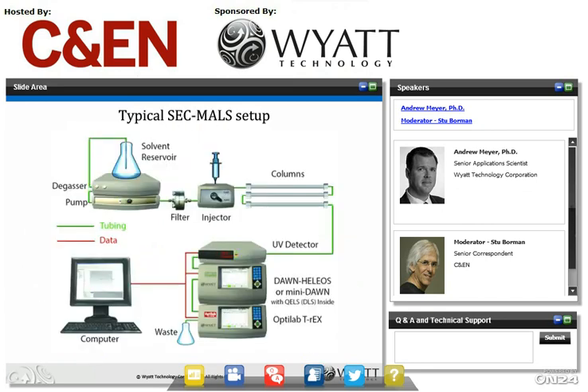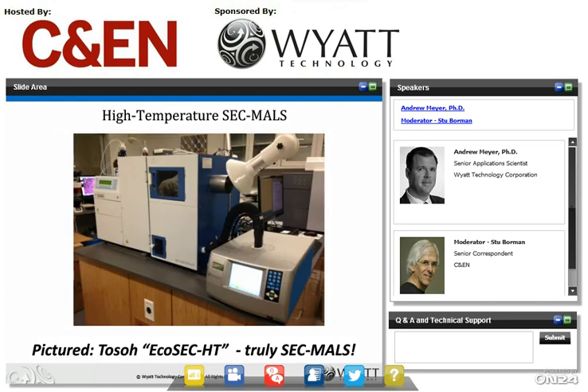In this slide we have a look at the complete SEC-MALS system. We've added a light scattering detector in front of the refractometer, and we read data from both instruments at the same time. We also have a UV absorbance detector available. This arrangement will work with just about any solvent, just about any GPC column, typical flow rates and conditions, room temperature, elevated temperature, and so on. We can take this up to temperatures over 200 degrees Celsius. Here as an example we see a MALS instrument interfaced with a TOSOH EcoSEC HT system, and thanks to the configurable heated transfer line design, the MALS can be interfaced with just about any high-temperature chromatography system.